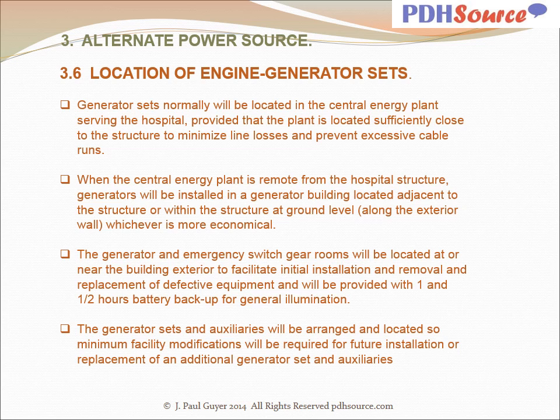With regard to the location of engine generator sets, they will normally be located in the central energy plant serving the hospital, provided that the plant is located sufficiently close to the structure to minimize line losses and prevent excessive cable runs. When the central energy plant is remote from the hospital structure, generators will be installed in a generator building located adjacent to the structure or within the structure at ground level along the exterior wall, whichever is more economical.